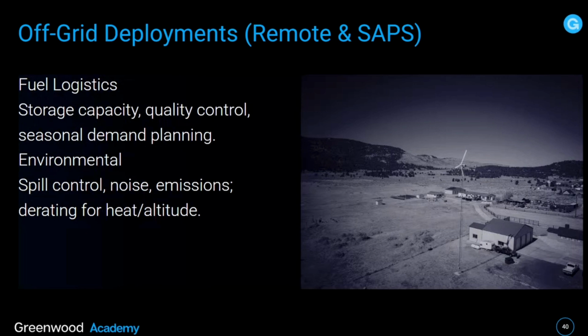It still needs to be exercised regularly. Fuel logistics is really important. Storage capacity, quality control, seasonal demand planning, environmental, spill control, noise, emissions, and derating for heat and altitude. This is a really important one. The higher you go, the more derating the genset is subjected to.